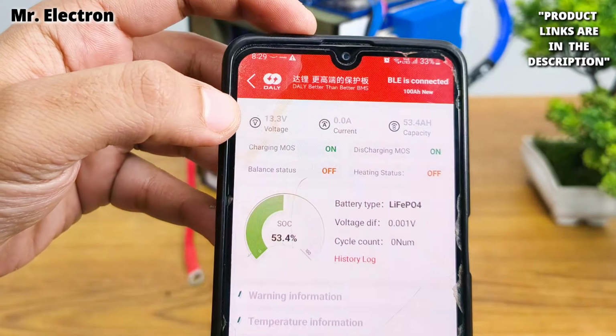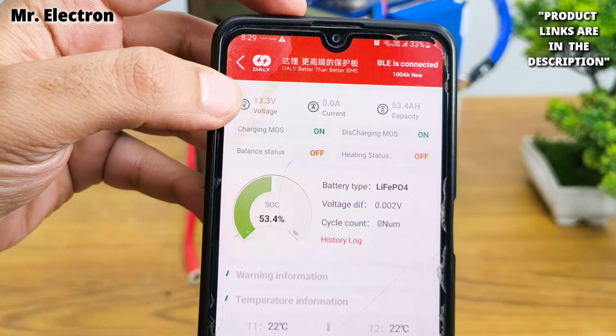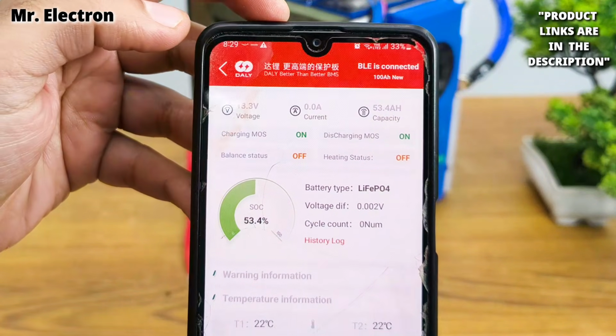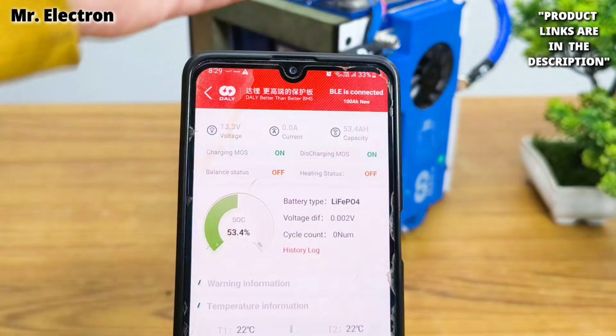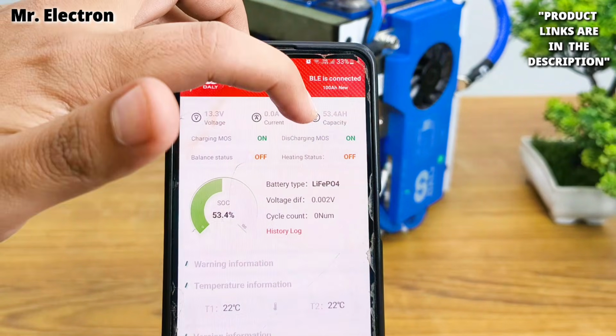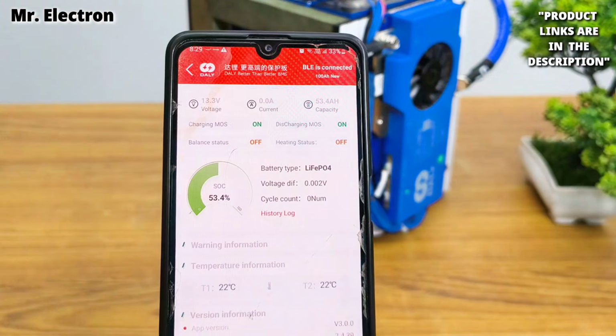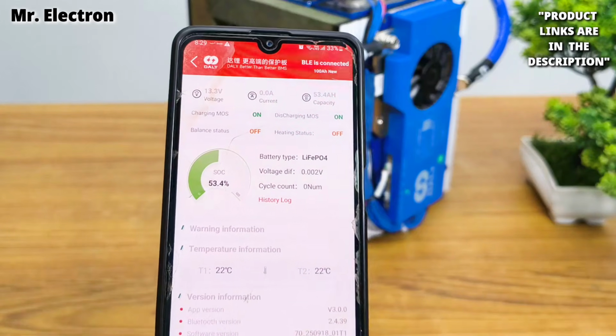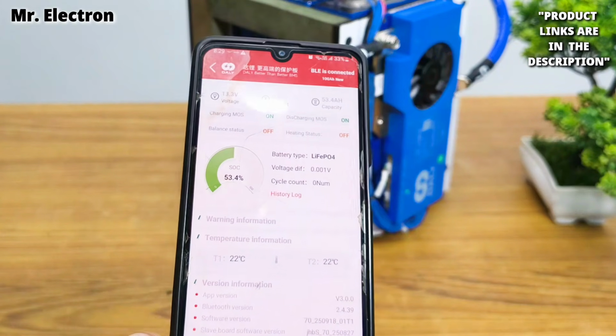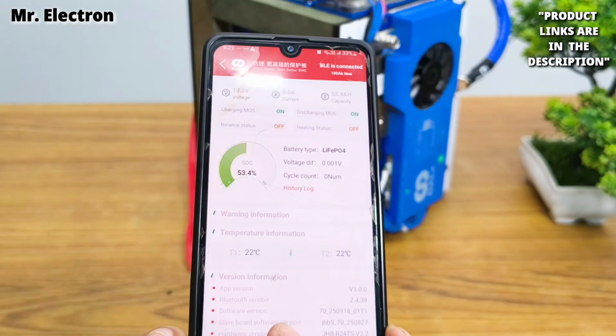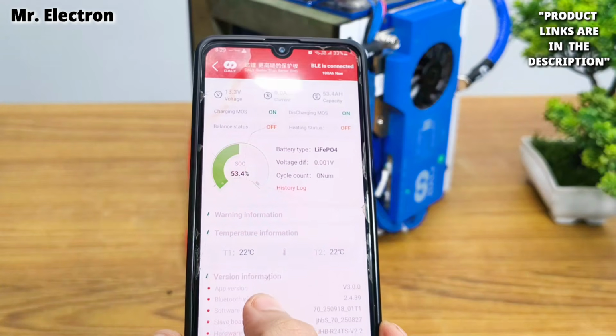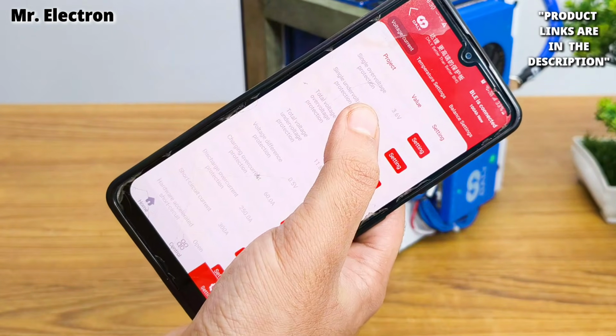Here you see the battery voltage, showing 13.3 volts, current being 0 amperes since it is not loaded at all, and capacity is 53 ampere hour - I think I will have to update it, it is not 53 ampere hour, it is 100 ampere hour. Anyway, the temperature sensors are measuring 22 degrees. Here are the settings - single over voltage protection is 3.6 volts.